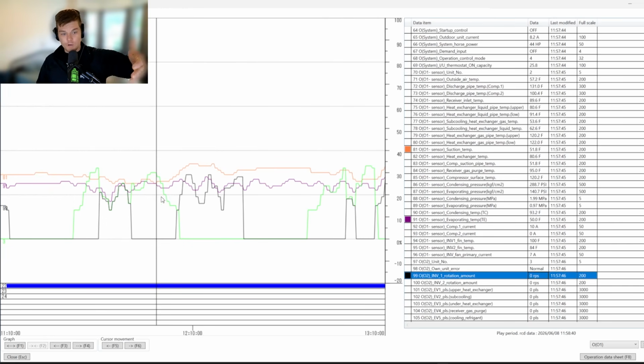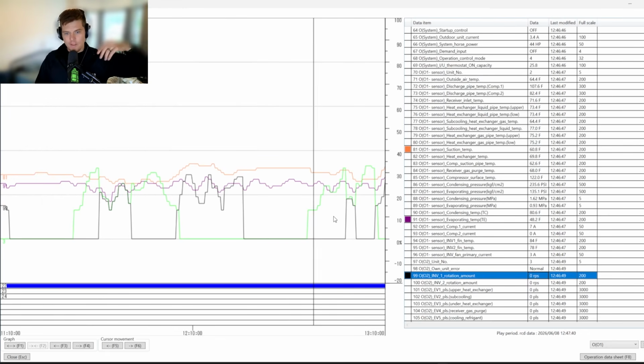You can see here when we're doing that, where this compressor has run for X amount of time, and then it's going to turn around and switch over. Now it's this compressor's turn. Well, guess what? Now the demand is not there. They both turn off. Then guess what? This one turns on, and that one turns on, and back and forth, back and forth, back and forth. We can go on all day about that.